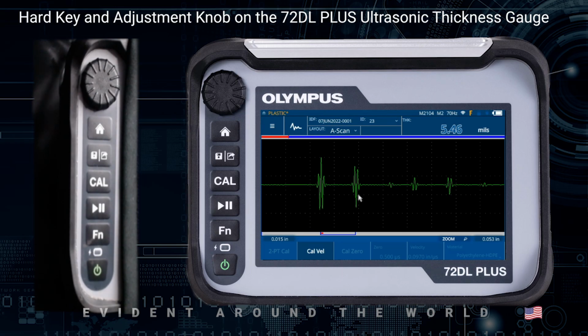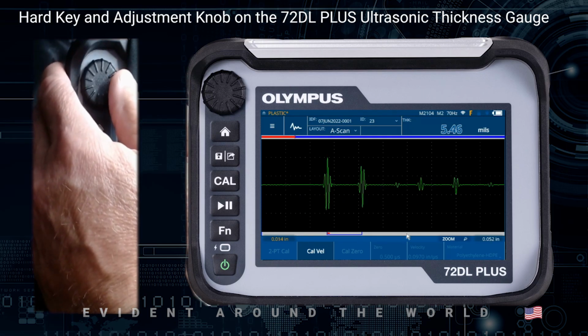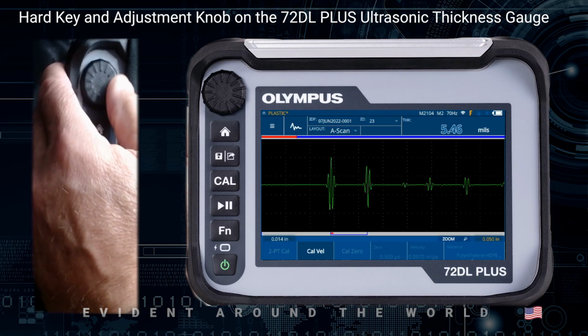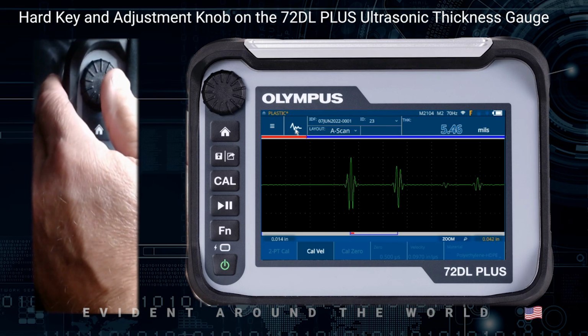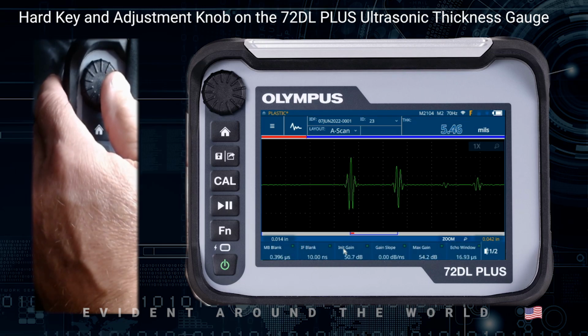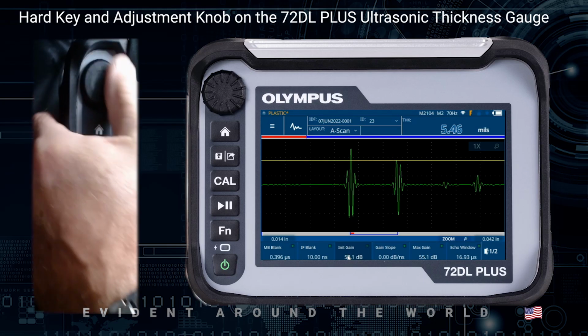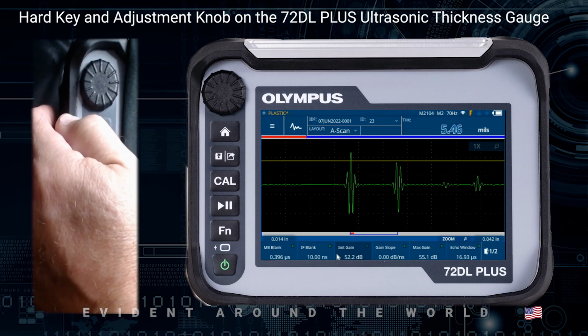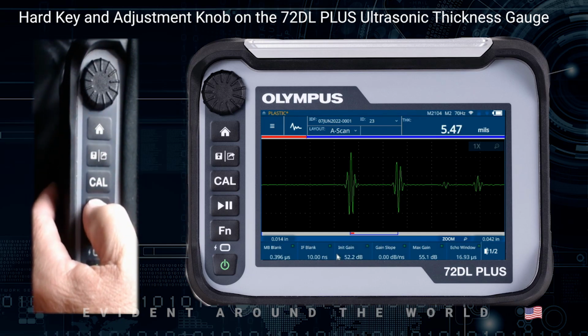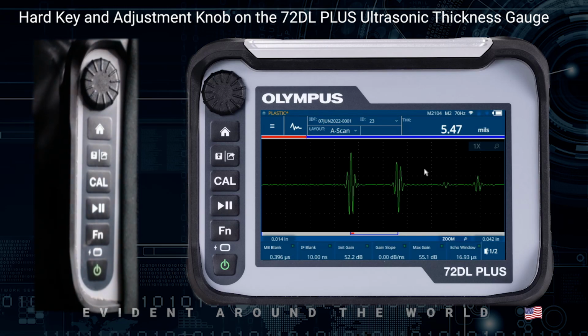The nice thing about the 72DL Plus is that because we capture all the data internally digitally, on a frozen signal you can simply adjust all the parameters for this measurement. So for instance, from a frozen waveform, I can go in and click on the delay and make adjustments to the delay. I can also make adjustments to the range. Not only that, but I can actually adjust the transducer parameters. For instance, if I want to increase or decrease the gain, I could simply go into the wave adjust setup menu, click on initial gain, and then using the knob, I could decrease and increase this all on a frozen waveform. Once I've got it set up the way I like, I could then unfreeze it by hitting the play pause key again, and now I'm back to a live measurement screen.